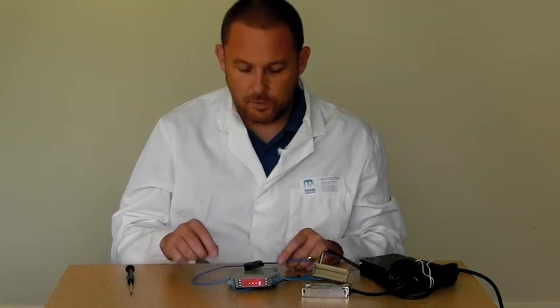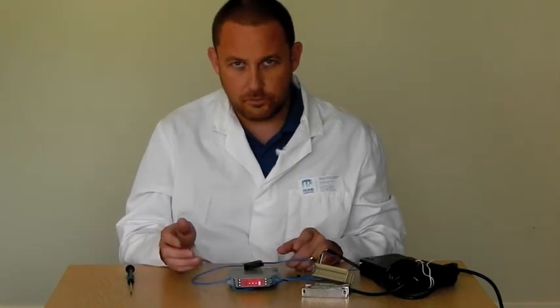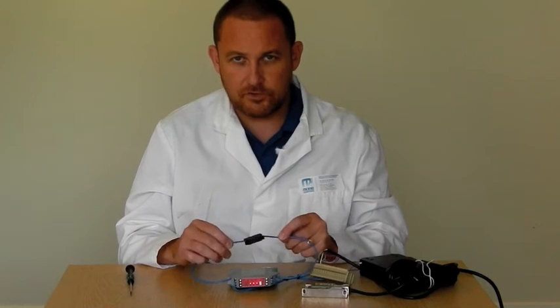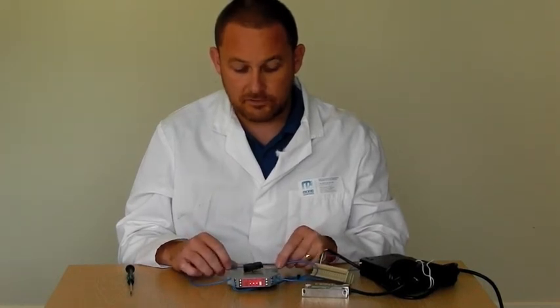So this particular safety relay can be configured to auto or manual reset. Before we had one loop in, which meant auto-reset. I've now introduced a reset button, making it into a manual reset type.